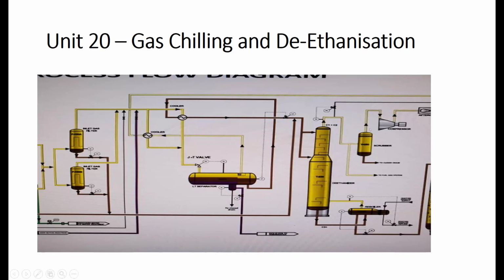So we have an overhead compressor that compresses the gas coming from the de-ethanizer to meet the 50-51 bar gauge pressure, in order for the lean gas, ethane and methane, to join and start its journey through the Twabo initial station on our 20-inch pipeline, heading to Kabwazi, to our non-power and power generation. Before it goes, it's metered, and your guess is right, you use an ultrasonic flow meter to do that.